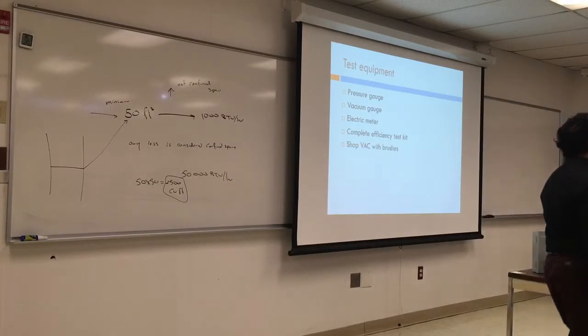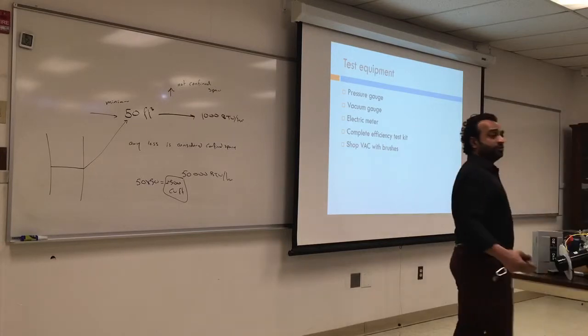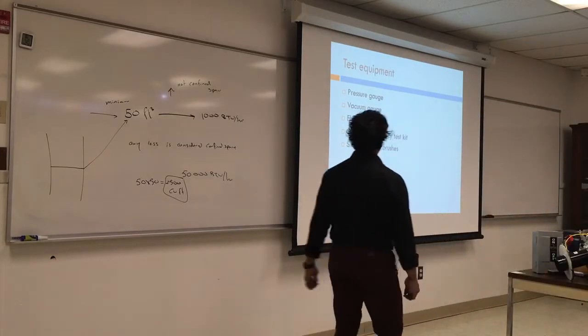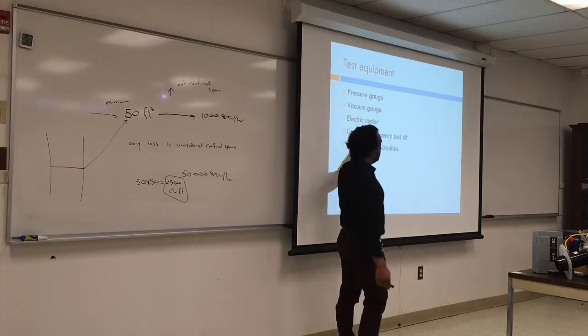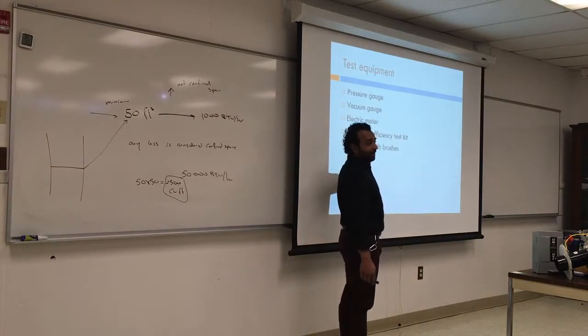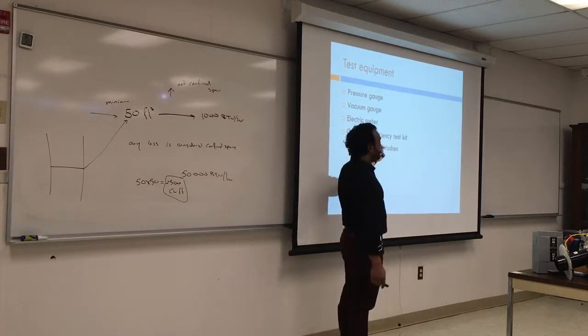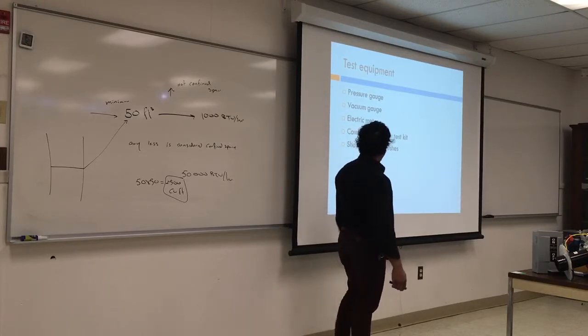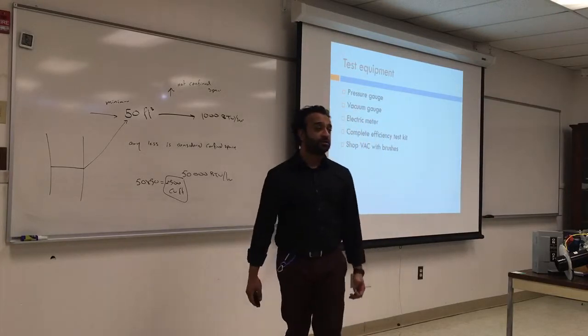Yeah, because you're required to have some suction, not a lot. Usually those things are gravity fed, they're not pulling from a lot of pressure, but they're required to have some suction for the resistance of the pipe and also for the distance. Electric multimeter, you need to have this with you the whole time. Complete efficiency test kit, and Shop VAC with brushes.